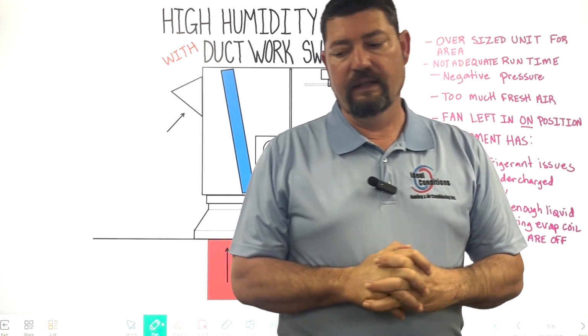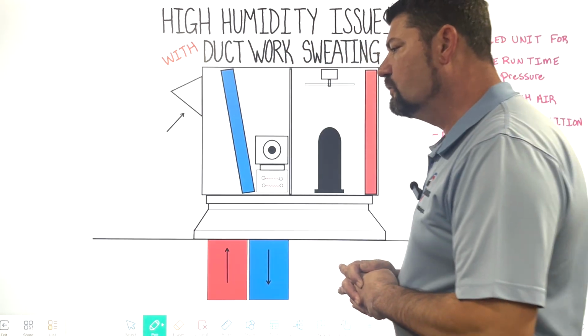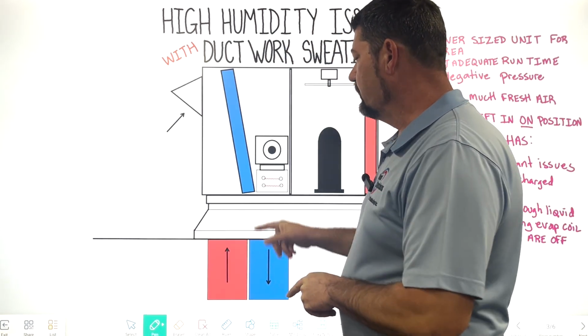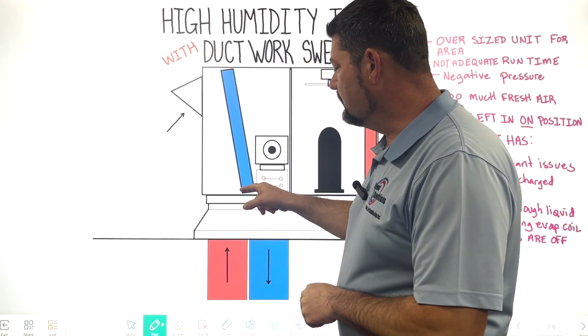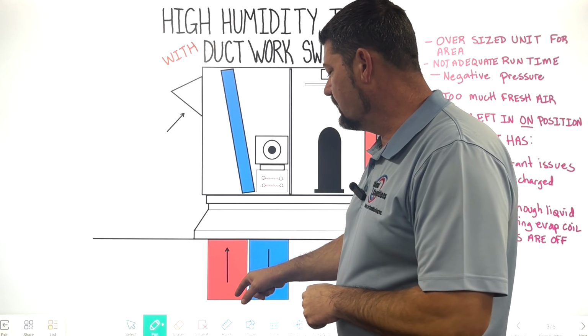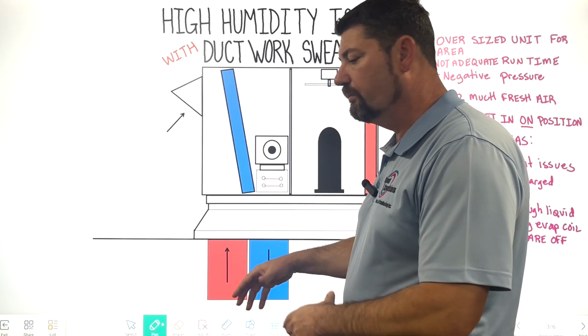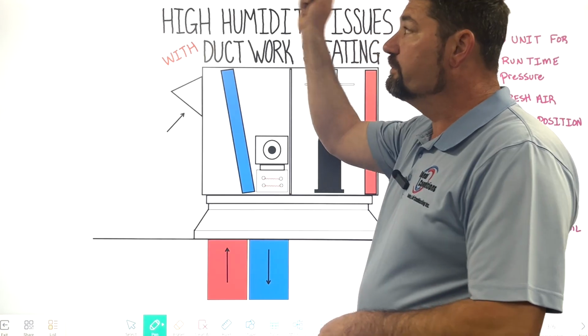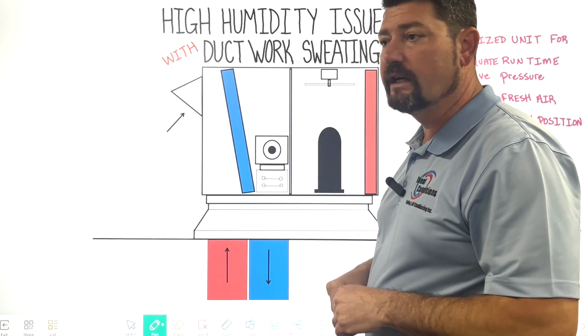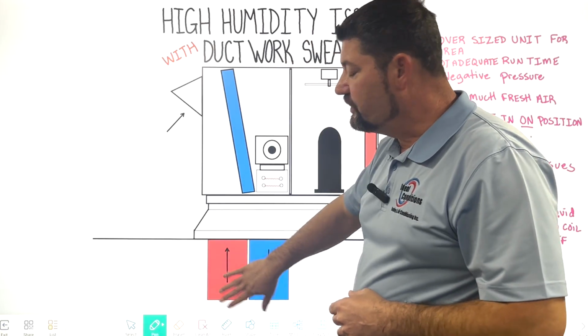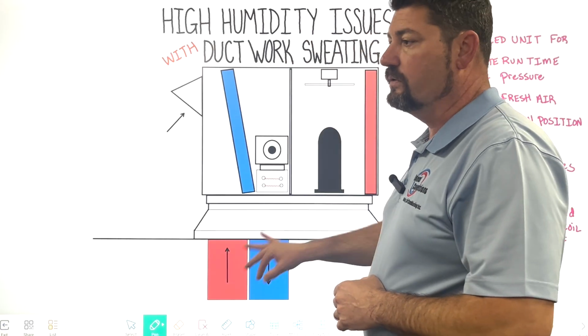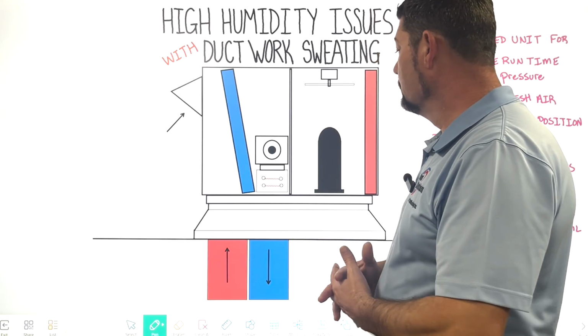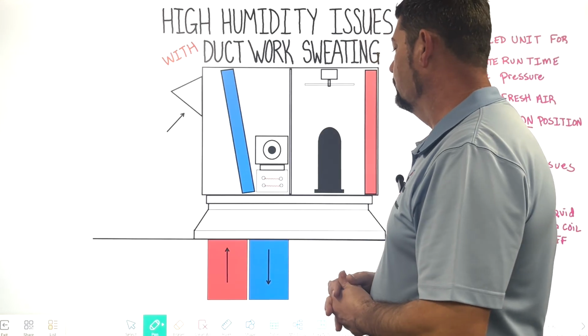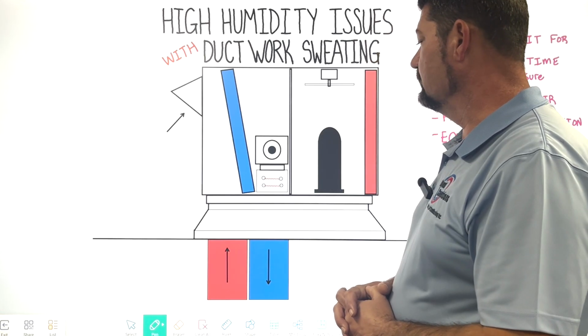One of the things that I see a lot of is people thinking that, oh, my ductwork is sweating because maybe my drain line is backed up and water has leaked into my return or supply duct, and it's just a pool of water and it's just dripping. They wind up cutting a hole and they find out that the plenum's dry. They don't understand, why is there moisture on the outside of the duct board or the metal or whatever, anything metallic. Tape, for example, has a metallic to it that will sweat.